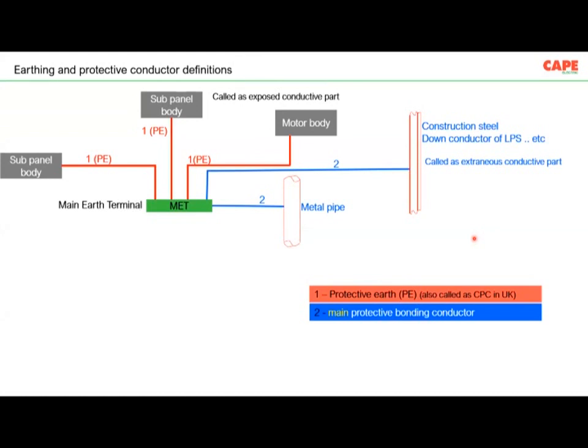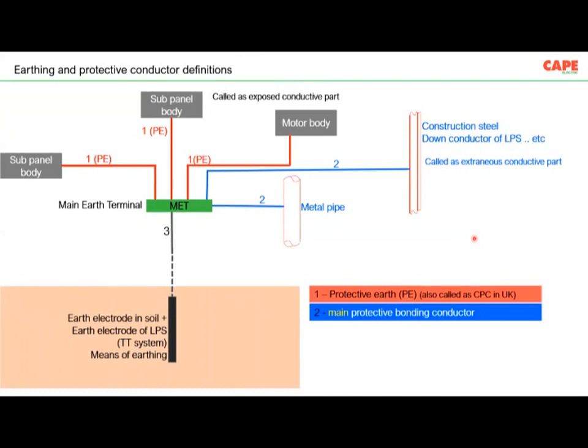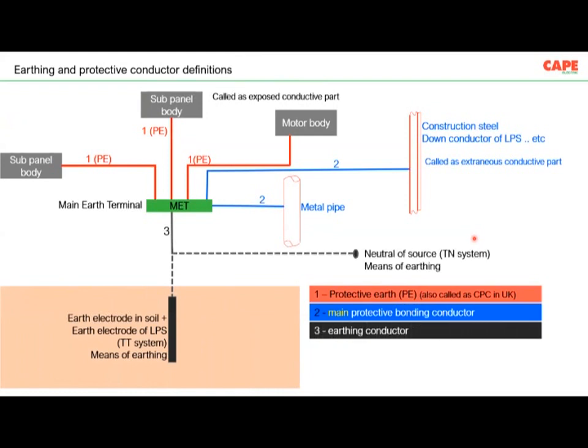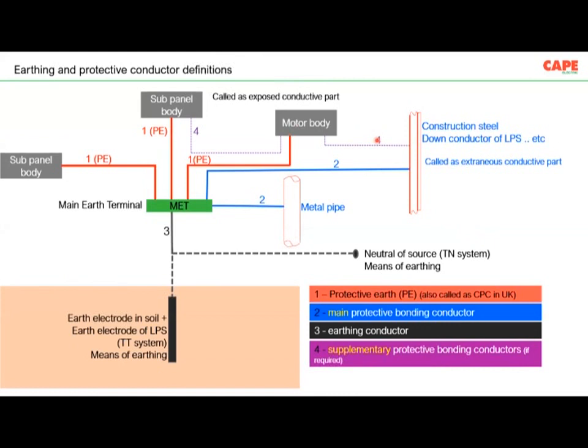That means at the mains incoming, the MET is very close to your mains incoming panel, the main switchboard, and at the main switchboard you are supposed to make protective equipotential bonding. Now, the MET is connected to an earth electrode in soil in case of a TT system, and these wires are called earthing conductors. The same MET is connected to the neutral of the source, which is also called an earthing conductor, in case of a TN system. In both cases, the source neutral and the earth electrode are called means of earthing. And an electrical installation also requires number 4, which is supplementary protective equipotential bonding. All these connections together are called protective conductors.